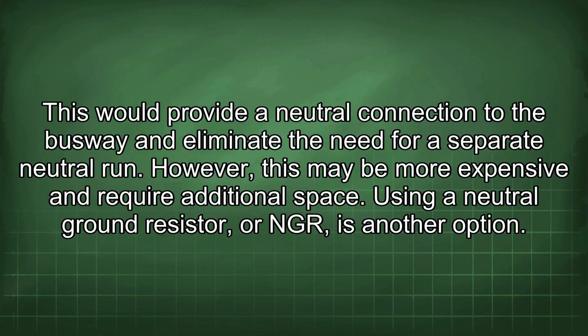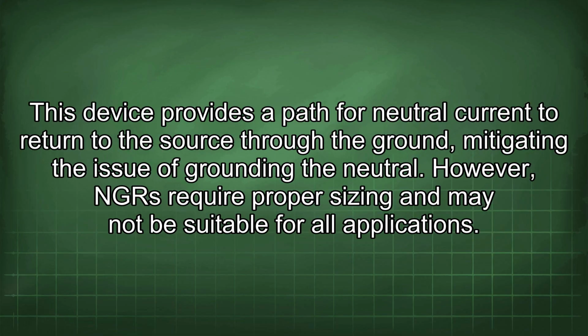Using a neutral ground resistor, or NGR, is another option. This device provides a path for neutral current to return to the source through the ground, mitigating the issue of grounding the neutral. However, NGRs require proper sizing and may not be suitable for all applications.